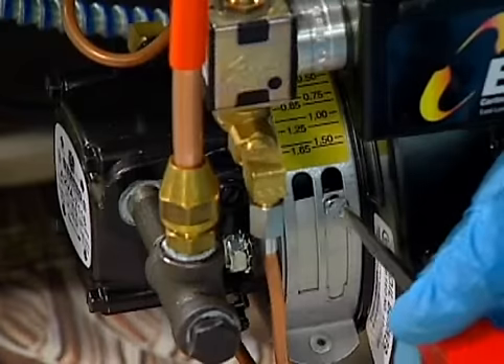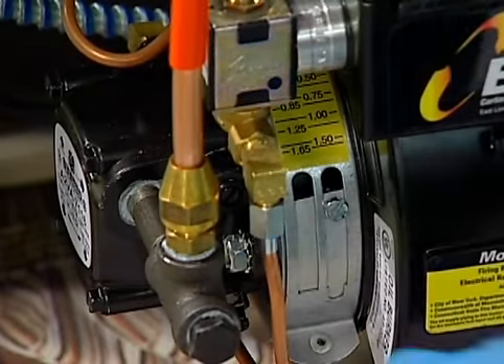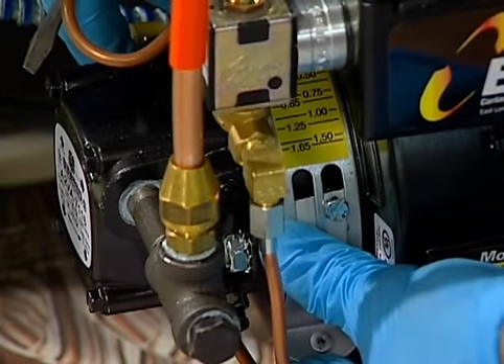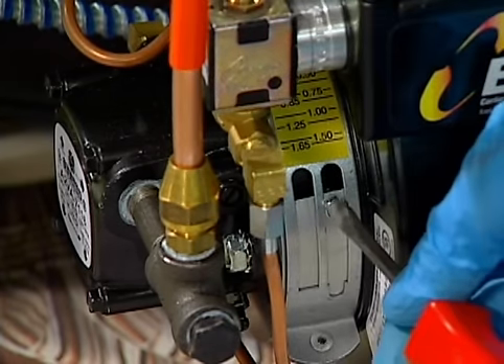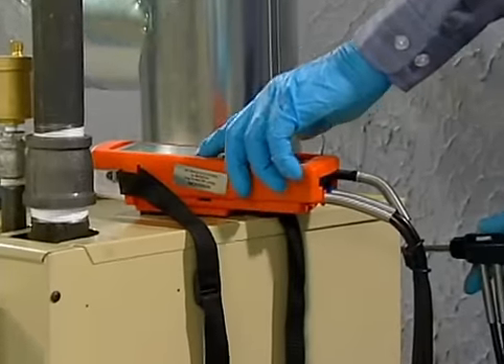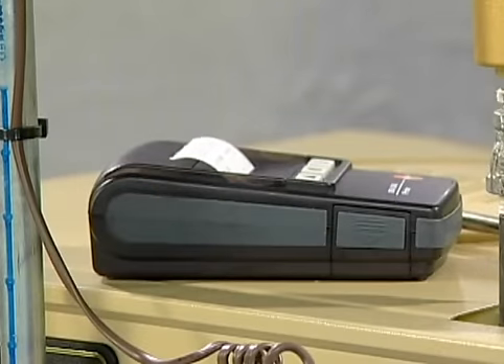Perform a smoke test, making slight air adjustments until the test produces just a trace on the test paper, or as specified by the manufacturer. Perform a complete efficiency test and record the readings. The steady-state combustion efficiency should be close to the following.